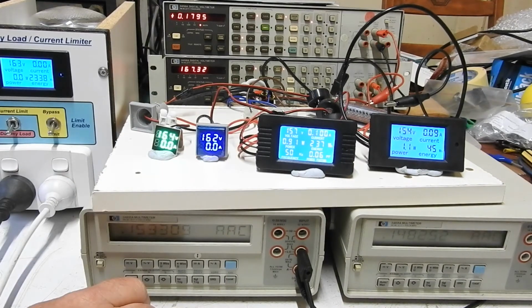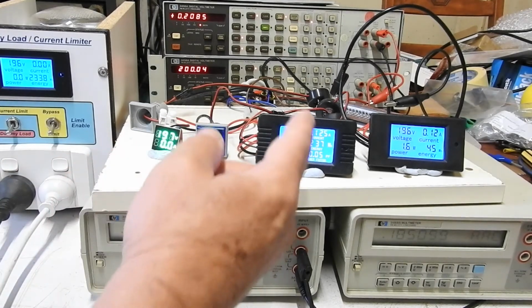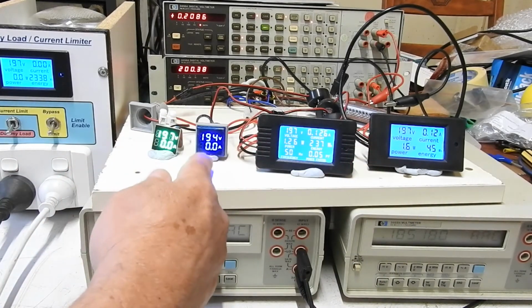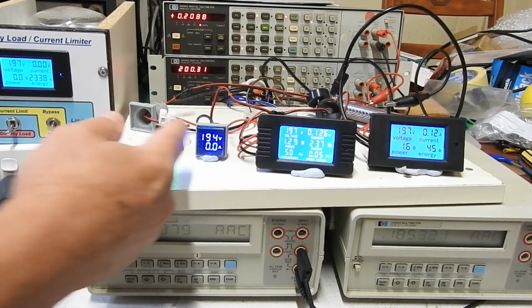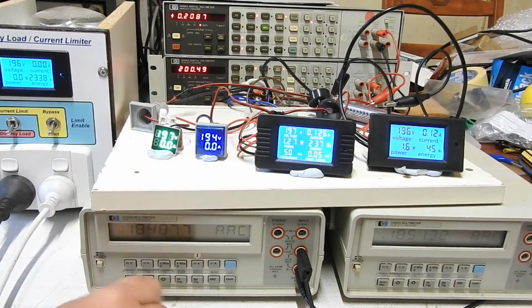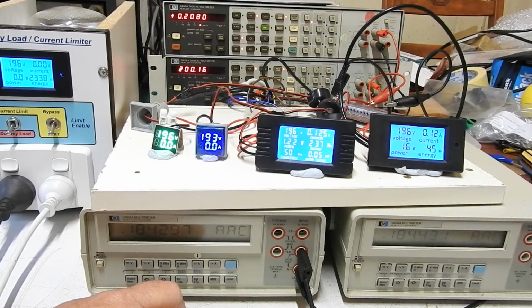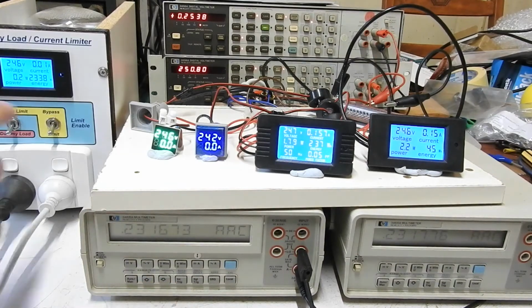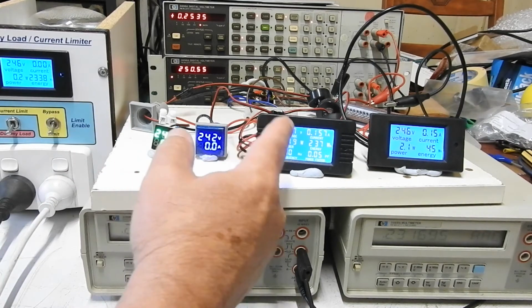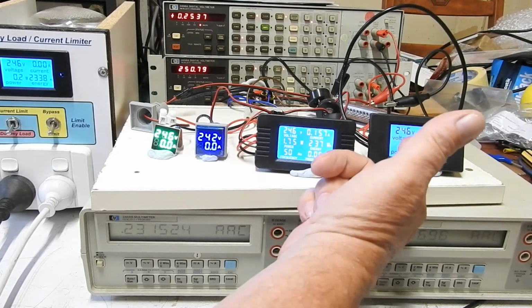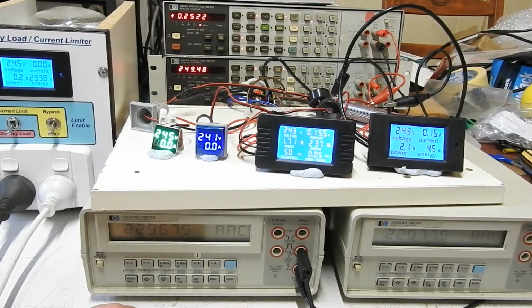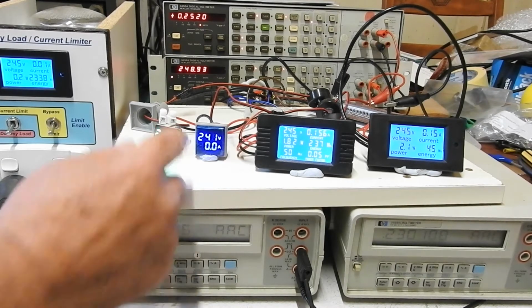200 volts: 196, 197, 194, 197, 196. Again, this one's the worst - about 3% out, the others within 2%. Finally 250 volts: 246, 246, 242, 247. So they're within 4 volts, and 1% would be 2.5 volts, so they're within 2% on voltage, except for this one.